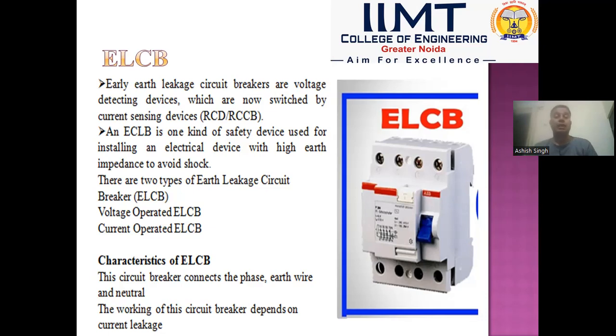Early earth leakage circuit breakers were voltage detecting devices which are now replaced by current sensing devices, RCD or RCCB. An earth leakage circuit breaker is a kind of safety device used for installations of electrical devices with high earth impedance, to avoid shock due to charge accumulated on the outer non-current carrying metallic part of the apparatus body. There are two types of earth leakage circuit breaker: voltage operated earth leakage circuit breaker and current operated earth leakage circuit breaker.